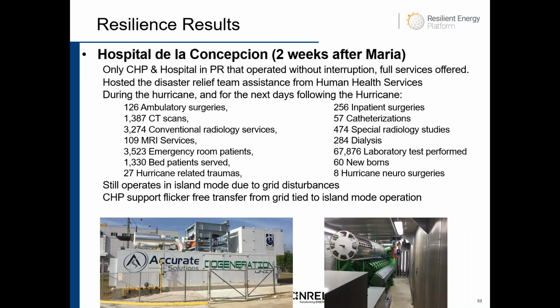We finalized commissioning of the second generator about 6 hours before Hurricane Irma arrived to Puerto Rico, September 7, 2017, even though the construction of the heat recovery building was not fully started, just the foundation. The hospital just disconnected from the grid an hour before the power was lost due to Hurricane Irma. Maria got us disconnected, and from the longest power outage in U.S.